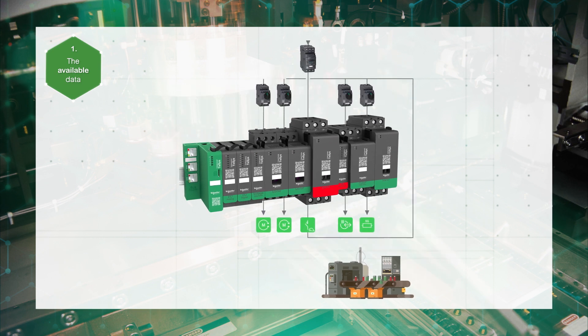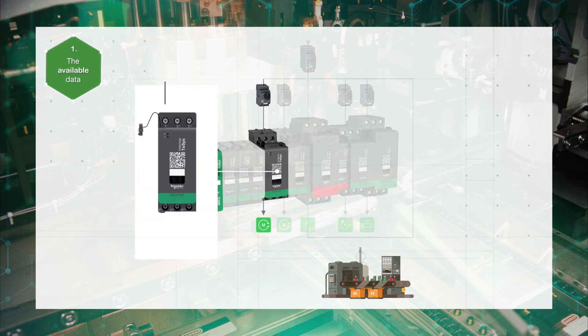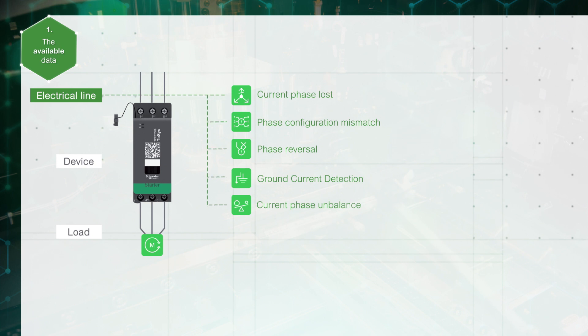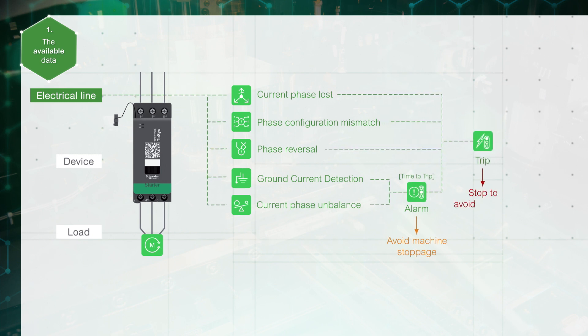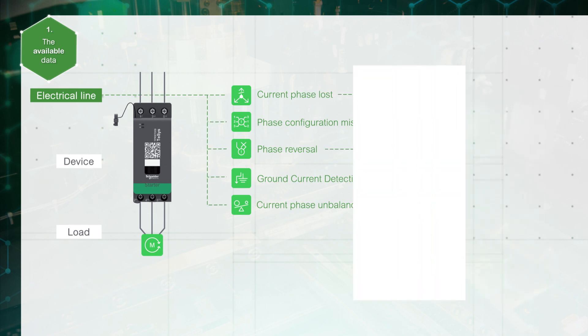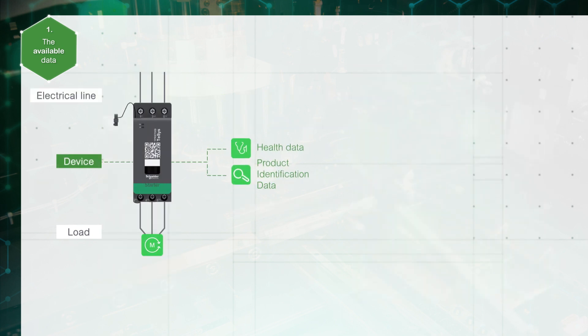Let's focus on this one-direction motor. Tesys Island provides data about the electrical line upstream the device and the load. At the electrical line level, data about the power supply status is available. This data can be used to send an alarm before the trip and protect the load. Users can set their own threshold using SoMove, EcoStruxure Machine Expert, or OMT.